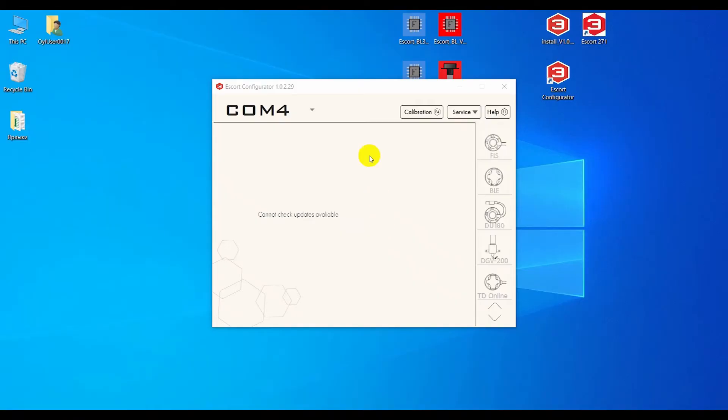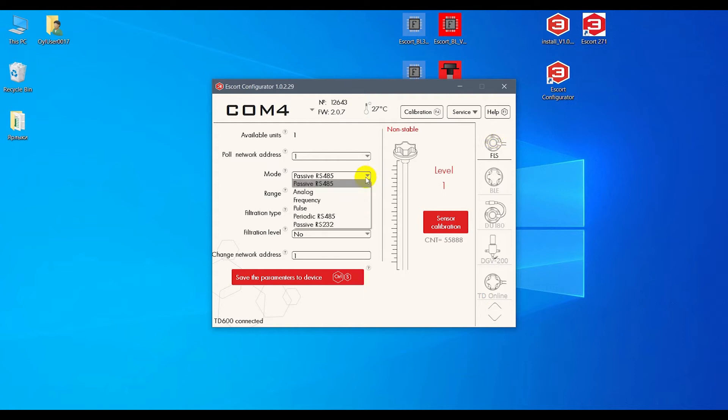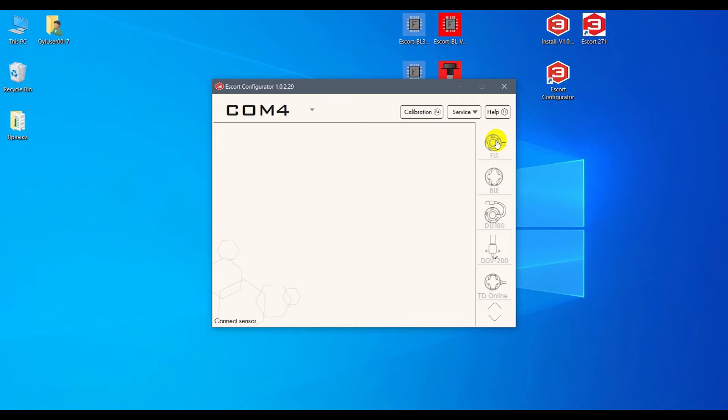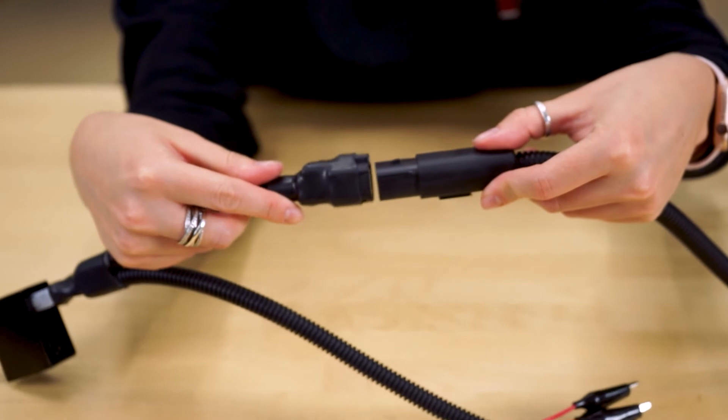All right, let's assume the sensor has enough power but still does not appear in the configurator. This could be due to the 15 seconds rule. If the sensor's operating mode is changed, for example you set a TD600 to the analog mode, the next time you connect it to your laptop you will have only 15 seconds to press the FLS button in the configurator program. If those 15 seconds pass before you click the FLS button, the sensor will not connect. If this happens, you need to reconnect the sensor and press the FLS button within the set 15 seconds.